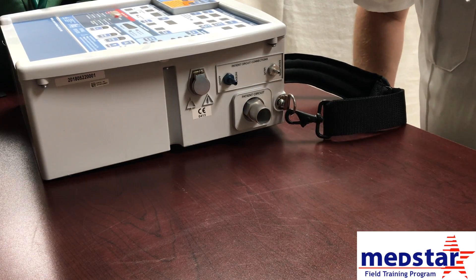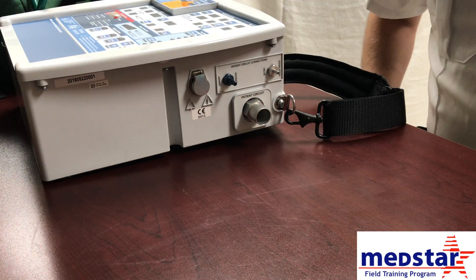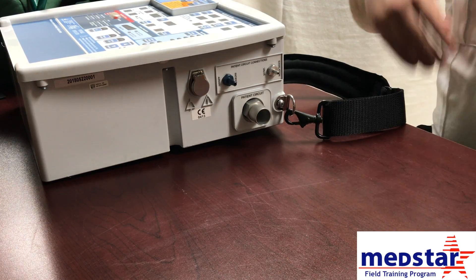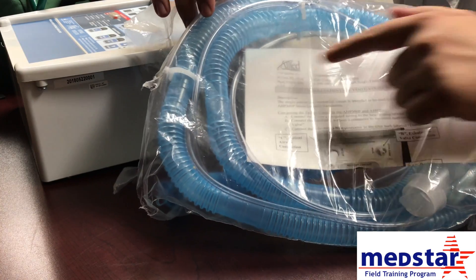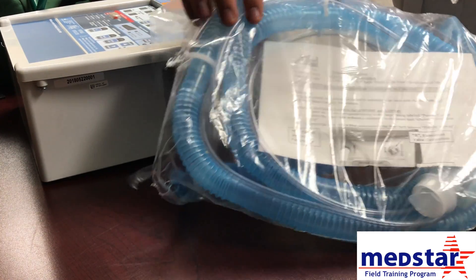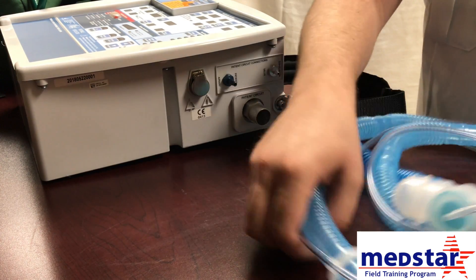In this video we're going to talk about how to set up the AHP 300 ventilator. The first thing we're going to do is look at the tubing. The tubing comes packaged like this — it is by Allied Healthcare and it is blue tubing. We're going to take that tubing out of the bag and show you how to hook it up to the ventilator.